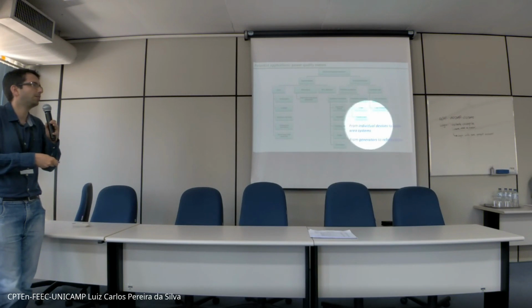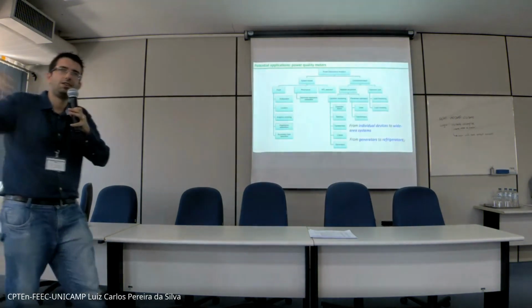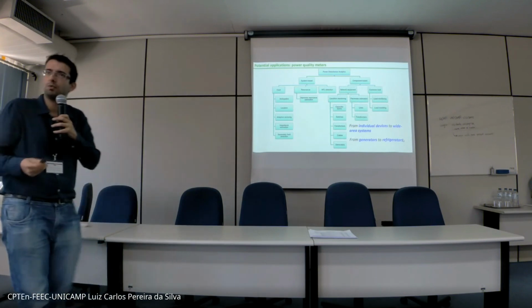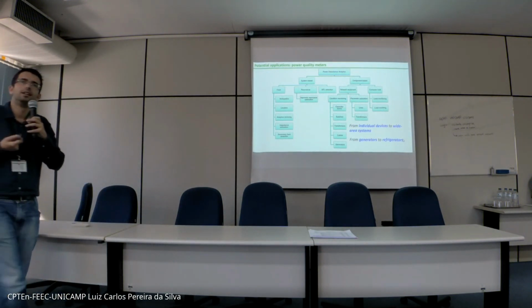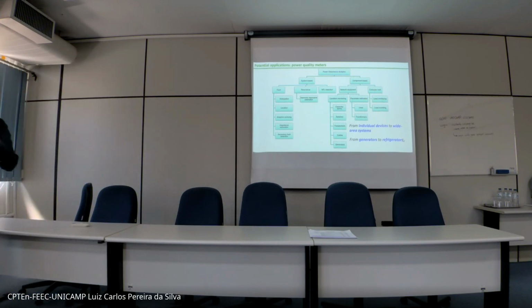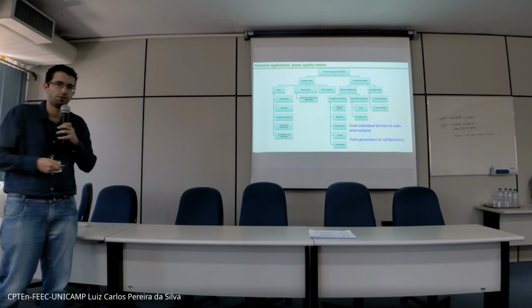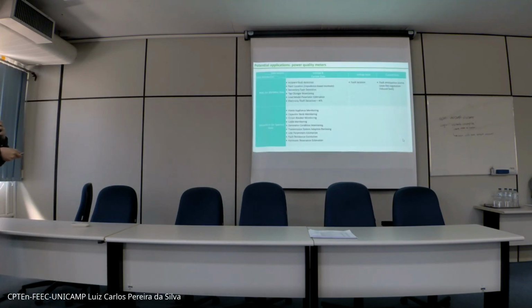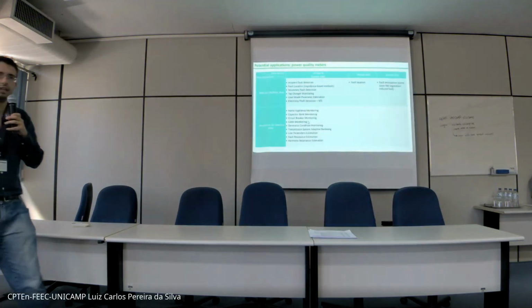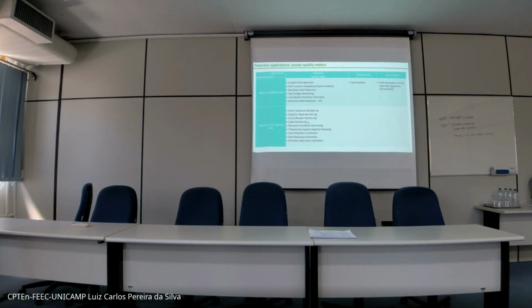I used to joke - though it's really true - that with this power quality meter data you can monitor from individual devices to wide area systems, literally from the big generators to the end customer loads. It's possible to analyze their operating condition and anticipate failures. This data can be used with RMS, and some issues can be detected with RMS data alone. But some issues really need waveform data, such as capacitor monitoring and cable failure.